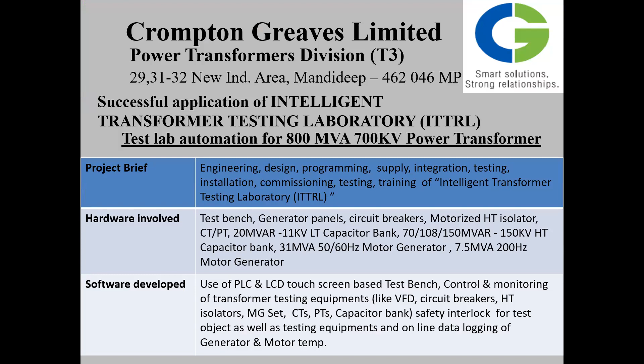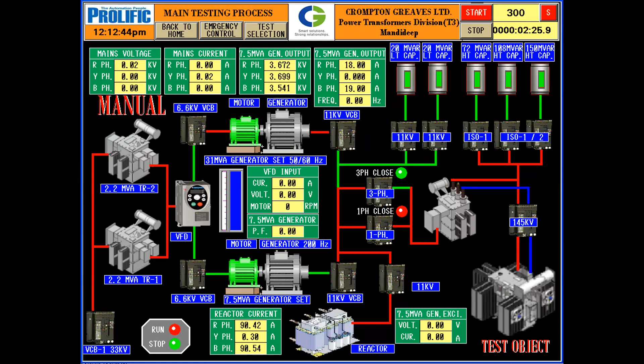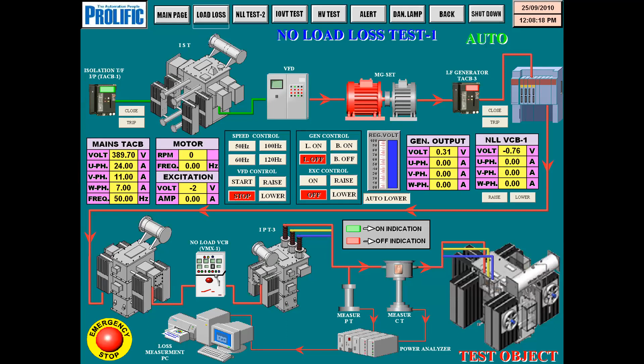This was for a job of 800 MVA, 700 kV power transformers. This was the test bench that was given. Another job, this was the graphical user interface for them. Then this was for the no-load loss test, the power distribution circuit.